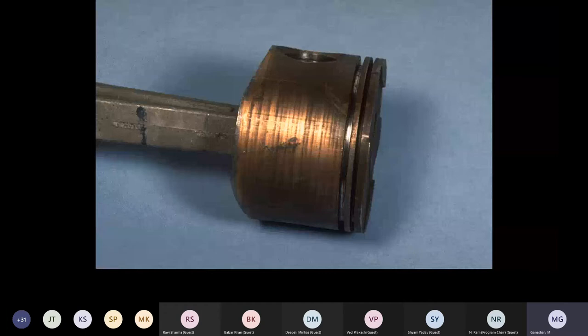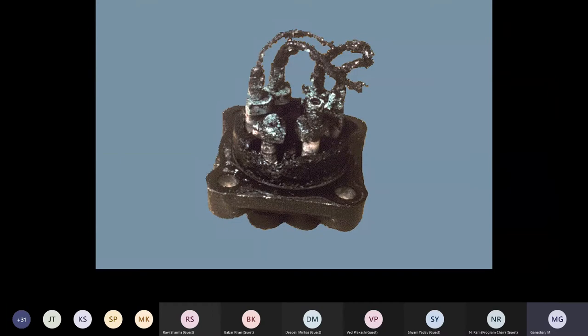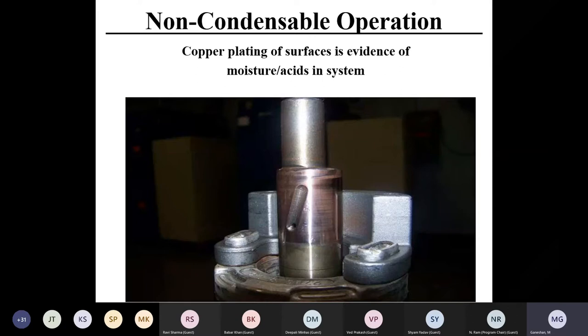You can see sometimes copper plating. Whenever we open up a damaged compressor, you can see shiny copper. This is nothing but moisture already being in the system, because it's like electroplating. It removes copper, and at higher temperature inside the compressor it deposits on the compressor. So this is an indication of moisture inside the system. This is again an indication of moisture, because it can eat away anything. The copper plating can also be because of the higher discharge temperature.